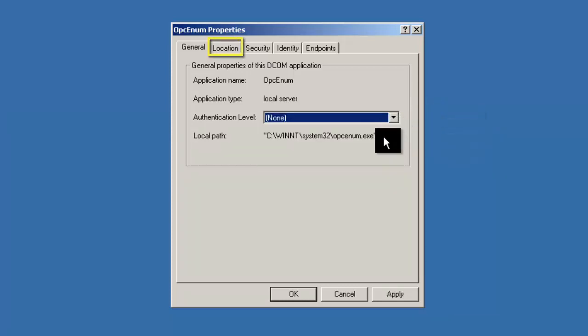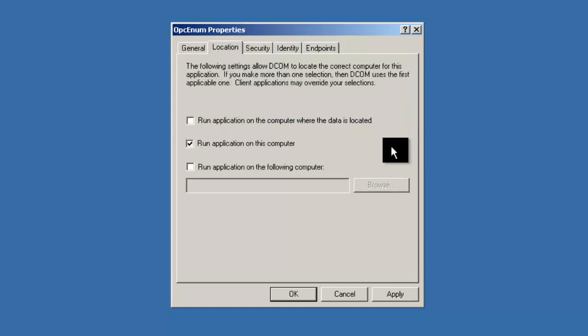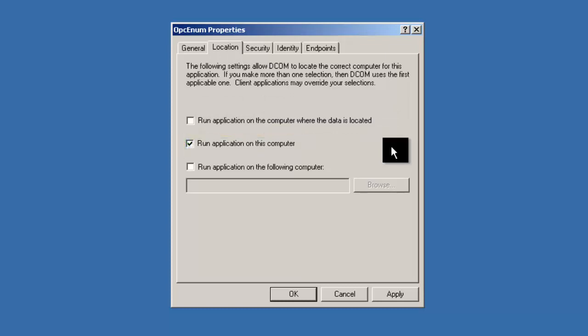Now at the top, click the Location tab. In the Location tab, ensure that 'Run Application on this computer' is checked. Since OPC-ENUM is a program that scans your registry for a list of OPC servers on your computer, OPC-ENUM needs to be able to run on the computer where it resides.